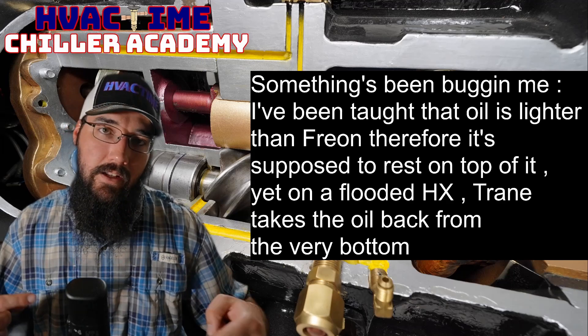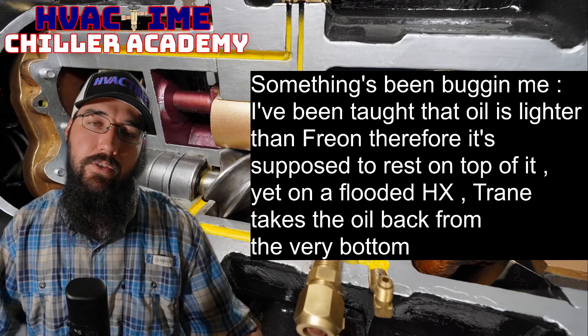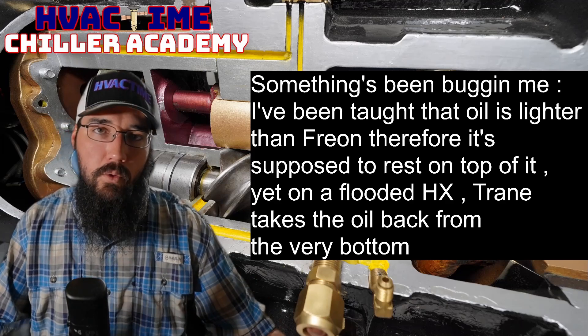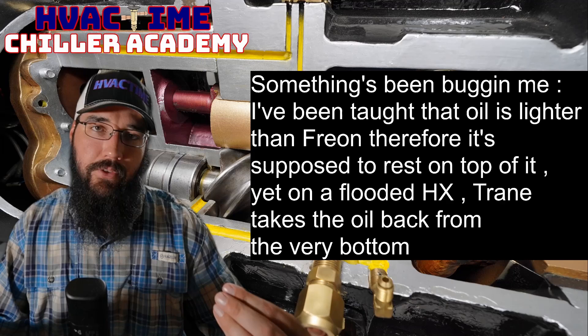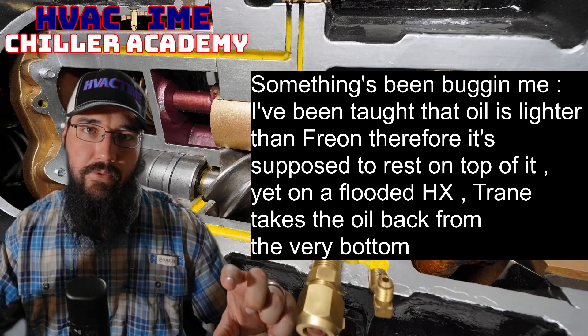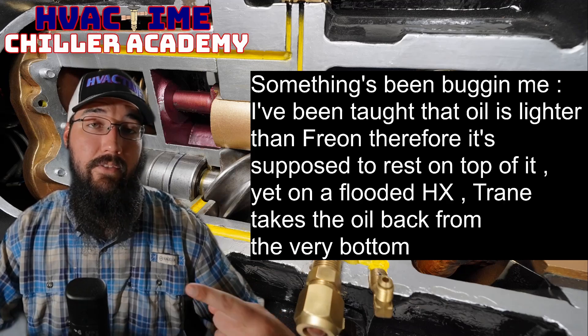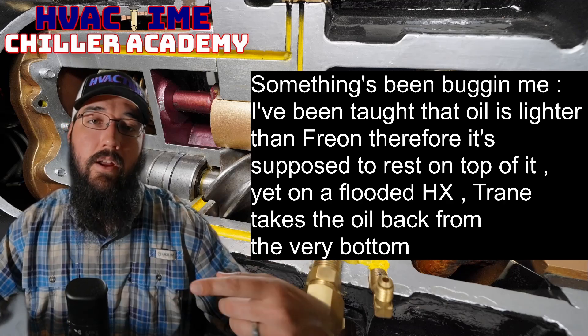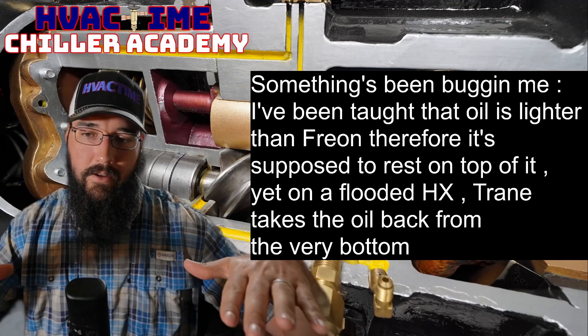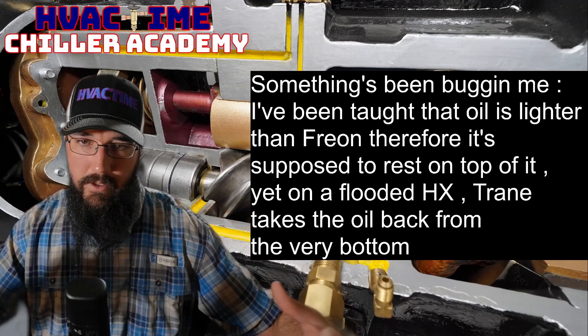These falling film evaporators have a very small amount of liquid actually standing in the bottom. Because that liquid level is so low, eductor systems — whether a gas pump or a jet pump eductor — can pull off the bottom of the evaporator. Within the refrigerant, the first few inches of liquid refrigerant is where turbulence occurs and where oil and refrigerant are heavily mixed. Oil sits on top but boiling is happening, so they're still mixed together — it's not stagnant separation while the machine is running.